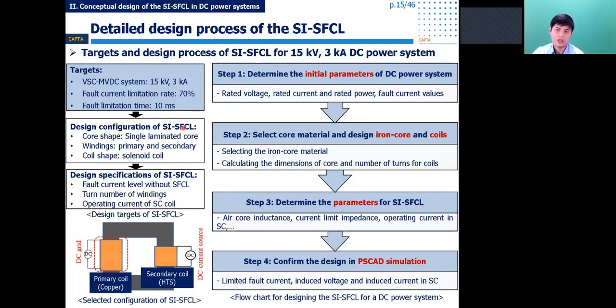Before starting the design of the SI-SFCL, a detailed design process is built. Firstly, the specification of the DC power system, including the rated voltage, rated current, rated power, and the fault current level, is determined. And then the core material is selected from the core properties and the DC grid parameters. The calculation of the core dimension and the core design are implemented. Finally, the PSCAD/EMTDC simulation model is built to analyze the fault current limiting characteristics. The design targets and the selected configuration of the SI-SFCL are shown here.